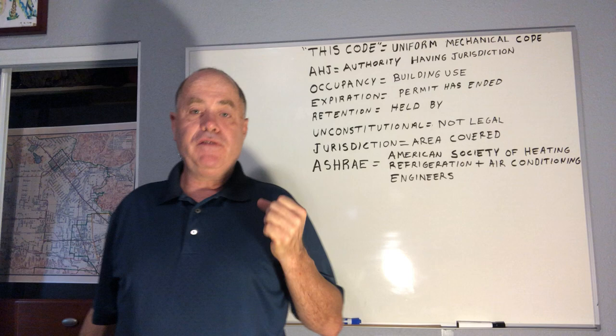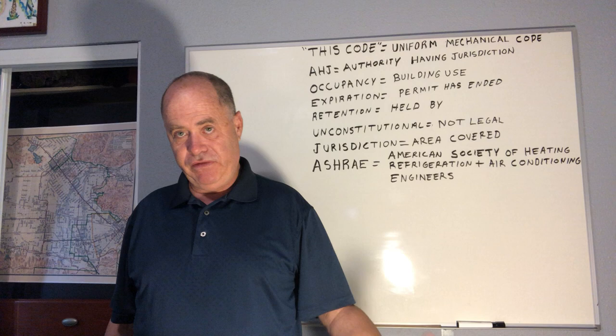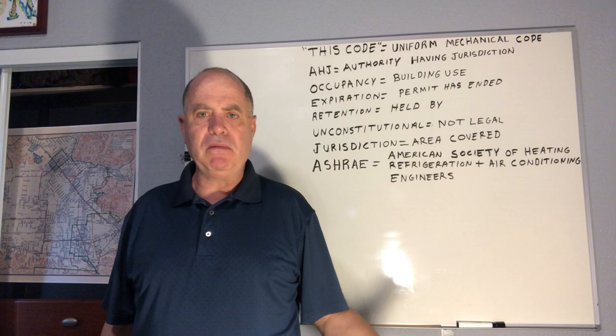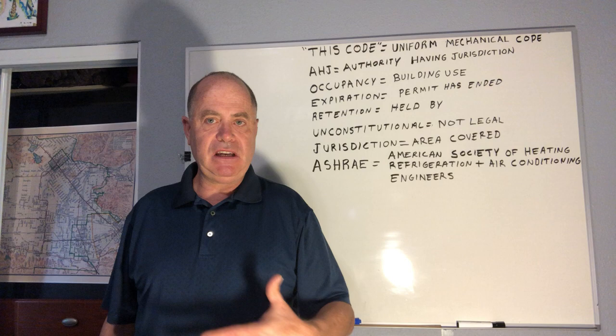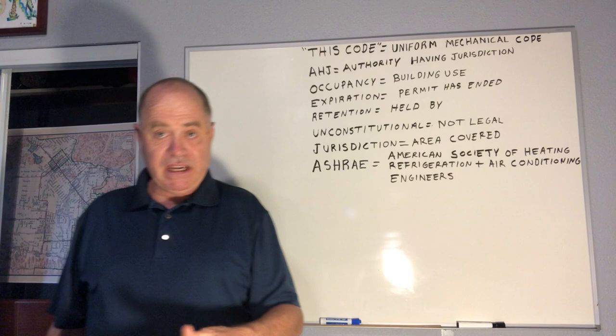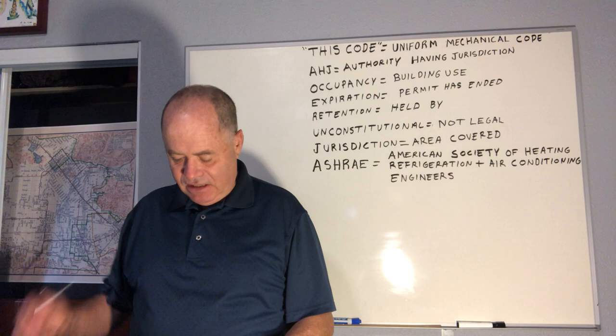The maintenance of mechanical systems is the owner's responsibility. The building owner is responsible for the safety and maintenance of the equipment, making sure it's installed correctly. Since the owner profits from the property, they have the financial responsibility to maintain it. This is based on the authority having jurisdiction — in Los Angeles, that's the Los Angeles Department of Building and Safety.